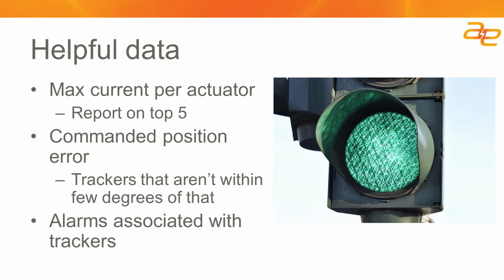Give me any tracker that isn't within a few degrees of where it's supposed to be pointing. That can be valuable. The tracker might think it's moving if there's a feedback mechanism, but it isn't actually moving. Maybe the tracker has gone beyond its movement range. If there's a rack and pinion gear system that moves the tracker, often if they move too far the teeth disengage and won't move back when the actuator tries to move them. So if you have feedback on whether the tracker is pointed near its commanded position, and it's way off, that might be something to look at.